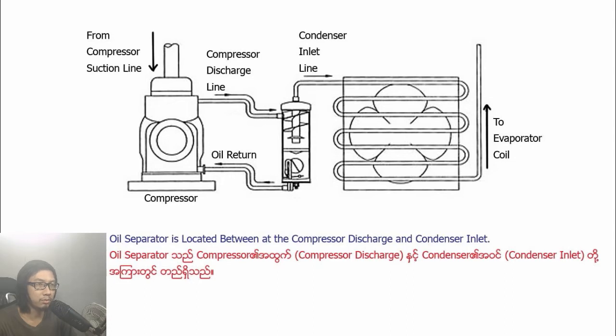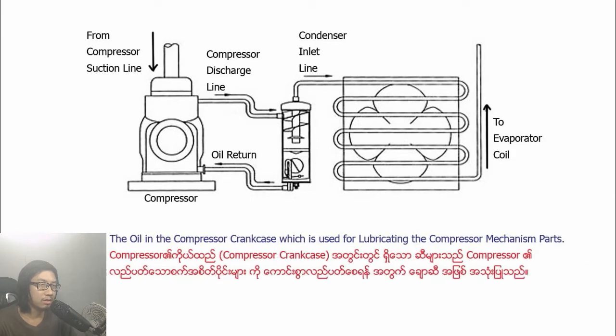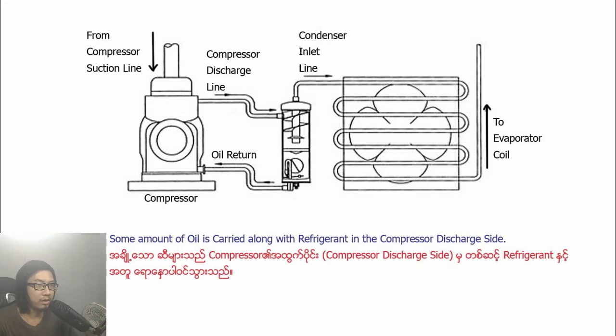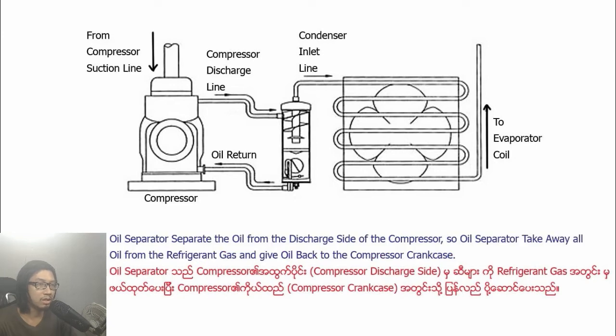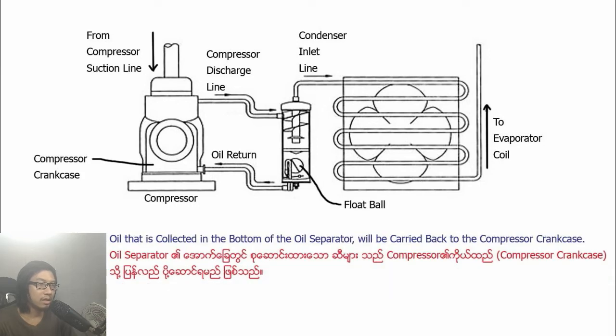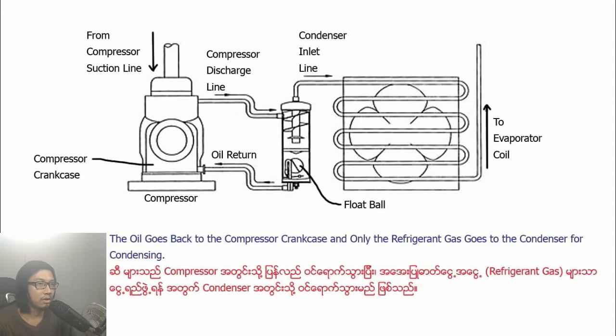The oil separator is located between the compressor discharge and condenser inlet. The oil in the compressor crankcase is used for lubricating the compressor mechanism, but some amount of oil is carried along with the refrigerant on the compressor discharge side. The oil separator separates and takes away all oil from the refrigerant gas and returns the oil back to the compressor crankcase. Oil collected at the bottom of the oil separator is carried back to the compressor crankcase, and only the refrigerant gas goes to the condenser for condensing.